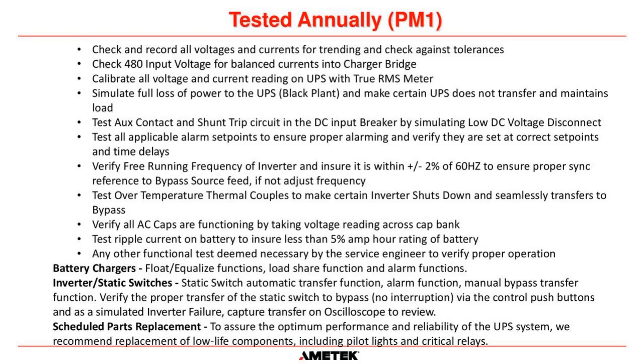So we do check and record all the voltages and currents within the UPS. And we don't just do it so we can put it in a fancy report. We do it because we're checking it against the tolerances of the system to make sure that everything that's being applied to that system is okay. Make sure that the 3-phase AC input is within the tolerances that are allowed, that the bypass input is within the tolerances allowed. We're checking all of these things.